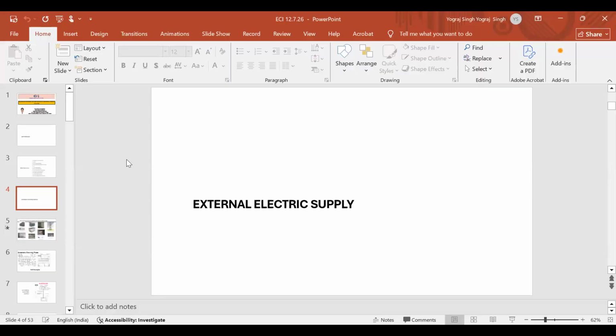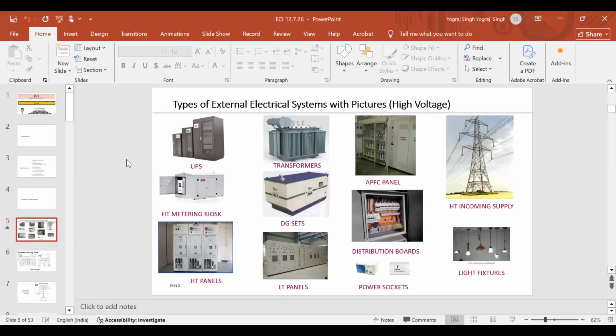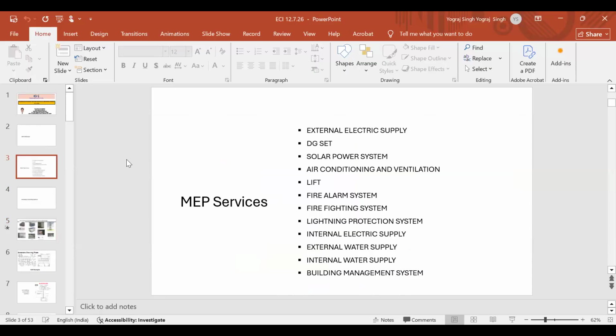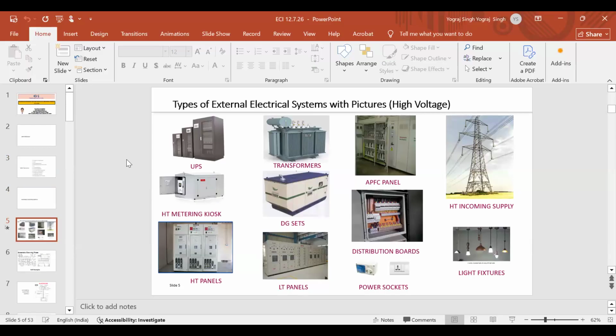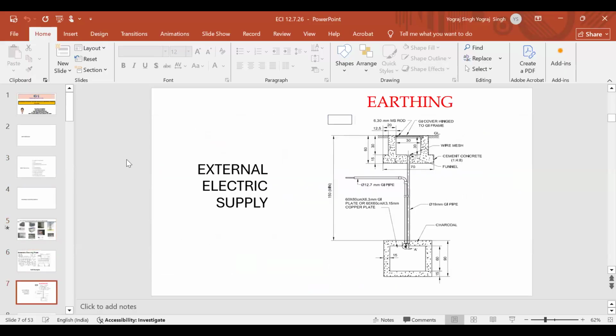Now, this is the sketch of an earthing. Why I have put this: earthing is a very common elementary thing. But what is there in earthing is not just the plate you can see down below. Somebody will say copper plate, somebody will say iron plate, and all those things. Those things are also required. Somebody will say chemical earthing. But the real earthing is the cylindrical shape around this plate, which is responsible for dissipating energy into the earth. Here the plate may be of gold, but if the earth around is dry and non-conducting, this energy will not dissipate into the ground. For that, that media is important.